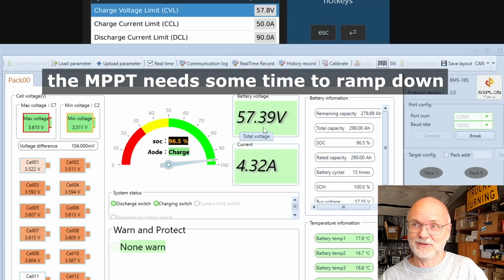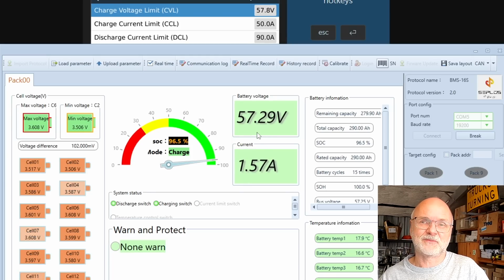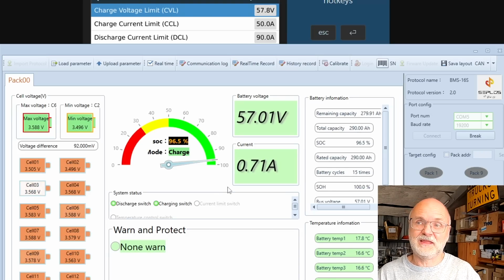This can actually happen when you charge that fast. So it throttles down, voltage comes down, everything is good. We are at 100 millivolt deviation now. That's why you have to set your pack over voltage alarm correctly, not to trigger it if you are overshooting your maximum charge voltage. So this has come down now to 57 volts. We are at 93 millivolt deviation, and the current has naturally tapered off to under 1 amp.